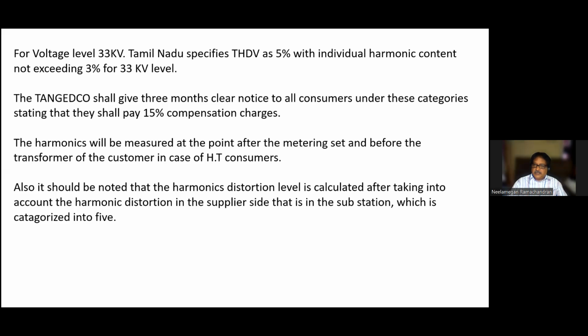They are going to measure the harmonics at the incoming, just after the meter and before our transformer. They are going to check this, and if it exceeds 5% for total harmonic content and 3% for individual harmonics, we are going to get a 15% penalty for this. So even though we are on 22 kV or 11 kV, most industries should be aware of this and should prepare ourselves beforehand.